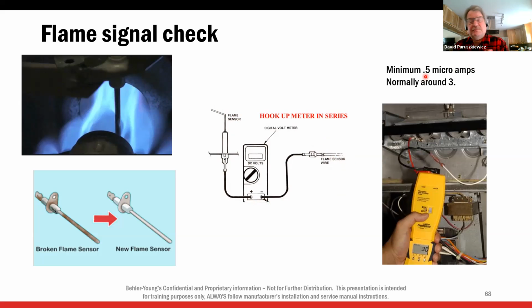Then we might look at the board, might look at the wire. So this is a very simple test to do, yet I get calls all the time. Well, the flame won't stay lit. It lights, it goes out. Well, what flame signal? This is really simple to check. You put your meter in series, you check your microamps, 0.5 or higher. 3 is pretty typical. And this is pretty much the same on anybody's.